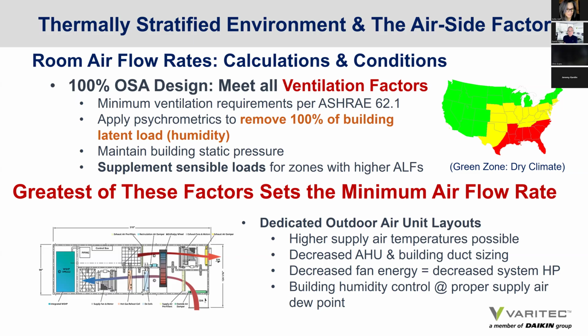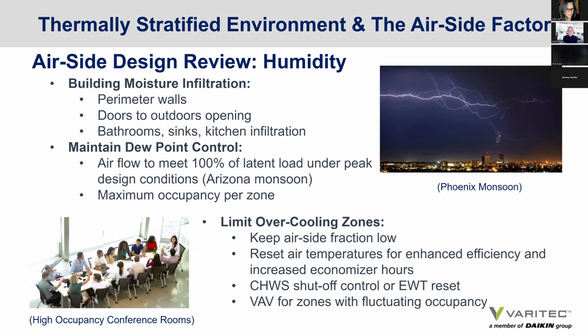So when you're looking at a dedicated outside air unit serving a thermally stratified environment, look at what the supply air dew point condition is and make sure that it's adequate, because buildings are continually being inundated by moisture. Again, going back to physics, moisture always moves from a high humidity state to a drier state. It's called latent energy and the vapor pressure effect. Again, wherever there's an imbalance of energy, high energy states move to low energy states. Well, a high humidity state is a high energy state. It will always migrate to low.